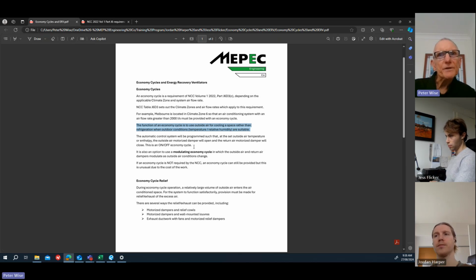So that's what I've said in the next sentence, basically. Where you have an on-off sort of situation, the outside air damper opens, the return air damper closes, that's basically, well, it's an on-off economy cycle. It's either on or it's off, okay? At that set temperature, it starts. When the temperature rises to whatever you determine is the right level, let's say 19 degrees, it turns off again and you go back to the normal cycle.